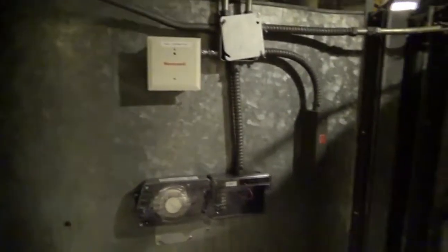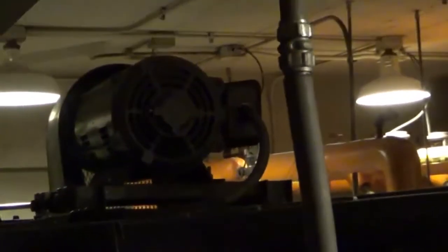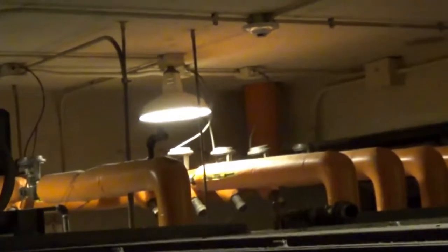So a mixed air handling unit is, we can either run chilled water through it, heat through it, or we can go ahead and open the damper on the outside of the building and pull cool air in when we don't really need to have the air conditioning. Motor sits on top. The orange pipes over there are low pressure steam pipes.